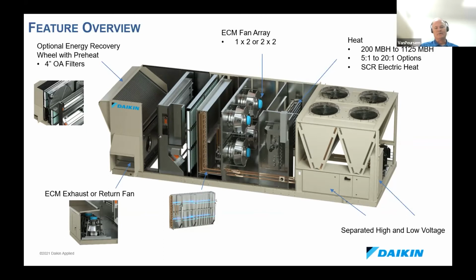Heat is no longer staged heating, whether it is gas, electric, hot water, whatever you may be using. It's more than likely you've been designing around tighter discharge air control, so you're using modulating gas furnaces and modulating SCR electric heat. All of that takes technology to integrate. Same way on the exhaust side, to better maintain the building envelope and the energy it uses with regards to building pressure, modulating exhaust fans or return fans maintain that building pressure precisely and more accurately, not wasting any energy. And any other ancillary devices such as UV lights or humidifier sections also take an analog type signal, requiring some type of controller to get that done.